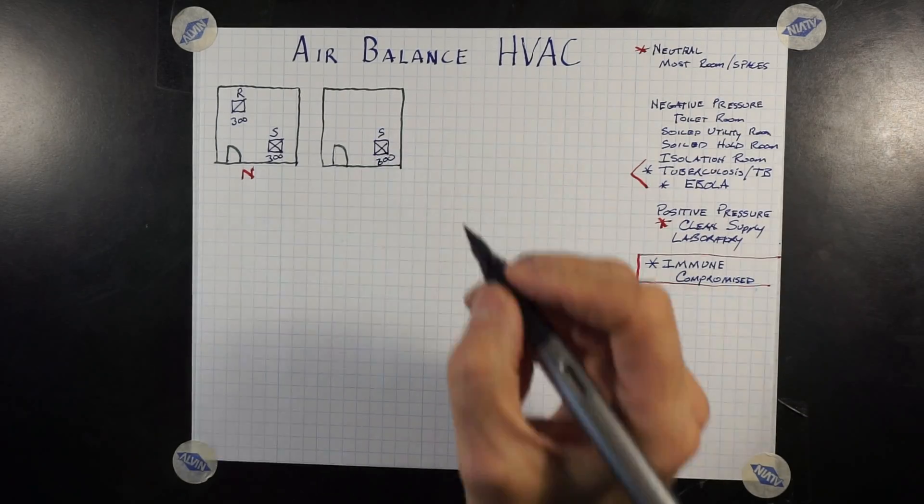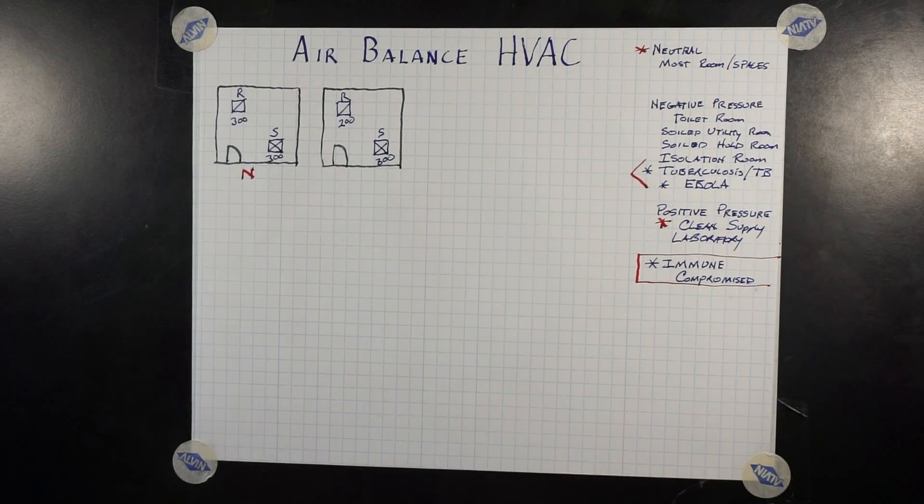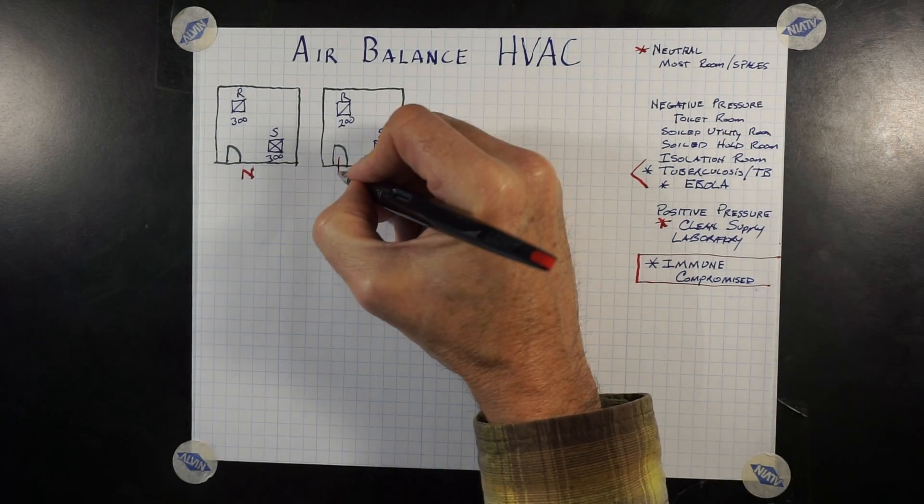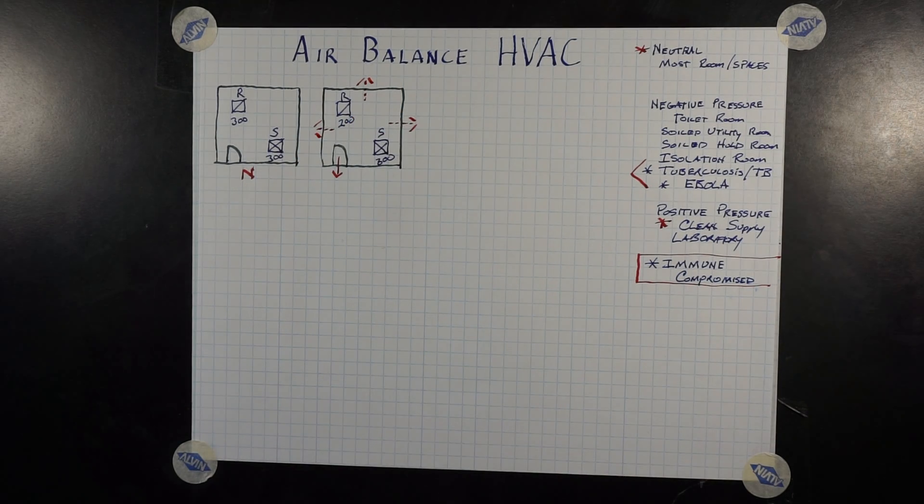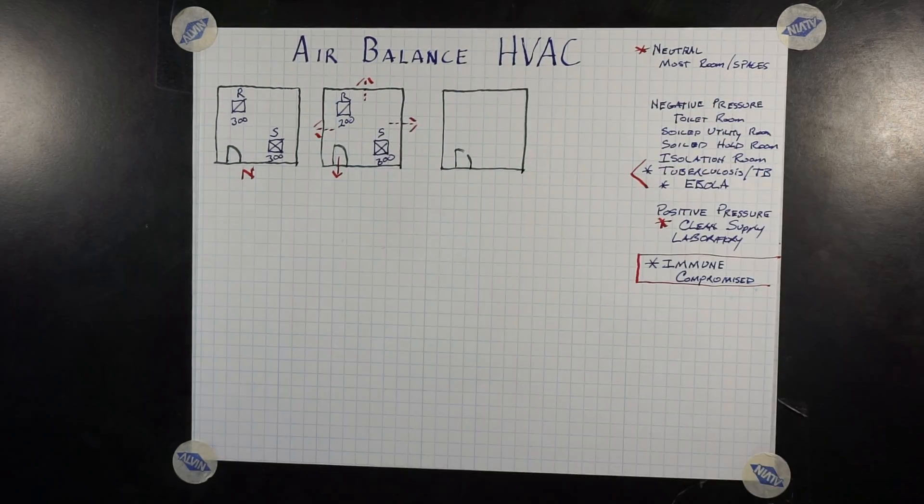With this room, we have 300 cubic feet of air coming into the space, the supply, and we have a return air of only 200. Therefore, any air that cannot be returned is being forced out of the room. And when the door is open, most of the air is going through the door. Otherwise, the air is being forced out through either the windows or the surrounding spaces or walls. It's got to go somewhere.